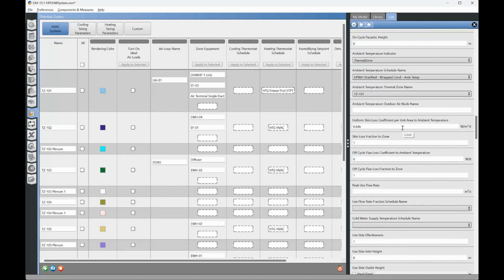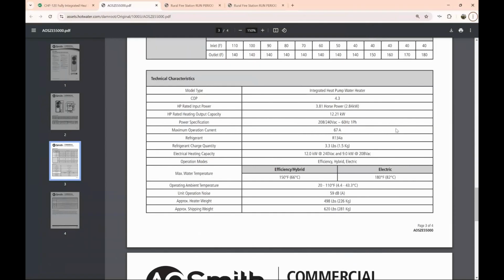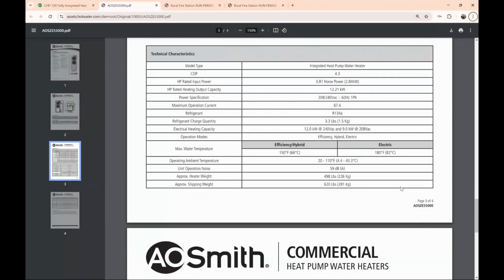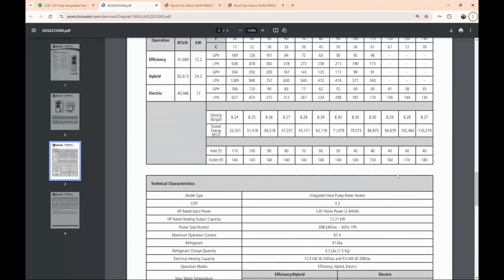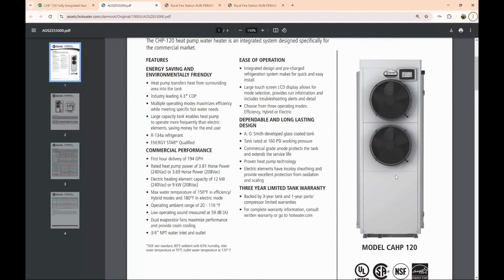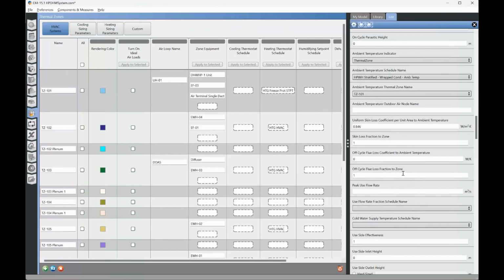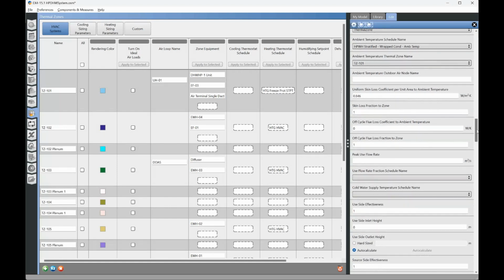Skin loss coefficient. This is probably not published on the manufacturer's information, so we can just leave that as a default. Skin loss fraction to zone. So this is saying, is this heater located fully in the zone, or is part of this heater located outside, somewhere else? But if it's fully located in the zone, which it most likely is, it's just going to be 1, which is 100% of that skin loss goes into the zone.